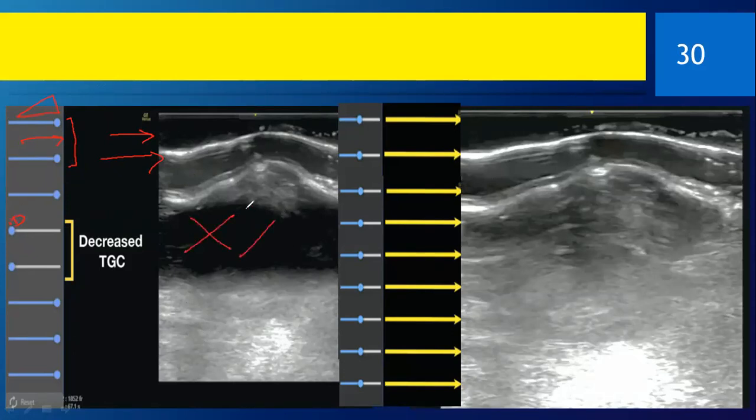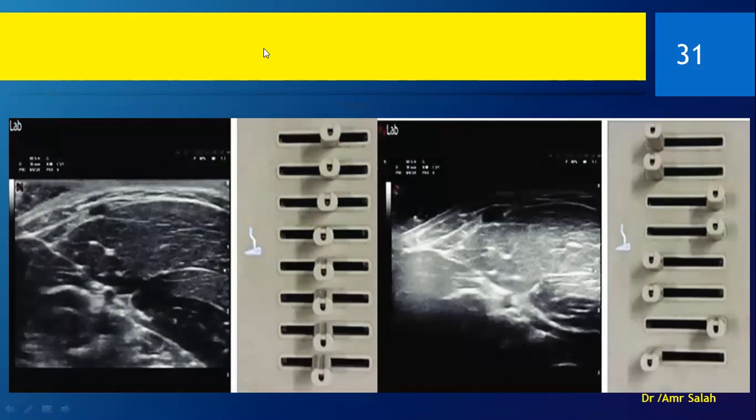No picture, absolute black. Again, when we move the lower sliders to the maximum end, where the wide end is, that is maximum brightness. So this is how we can control every part of the image by the TGC. Now if we set them all in the middle, we will see, as in here, the image will be in the shades of gray, no black, no white. To line the middle as such.